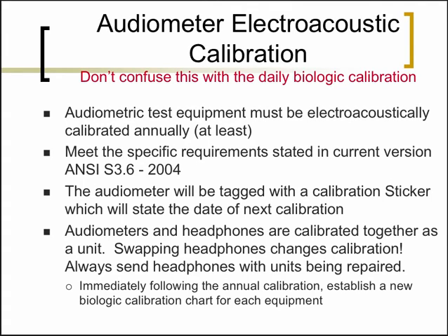So the second type of calibration, the more detailed calibration, is this electroacoustical calibration. This, as I've told earlier, is performed at least annually, and is often required by state and federal regulations to be performed periodically. The intent of this calibration is for the audiological equipment to meet certain standards. And the most recent standard that present-day calibrations need to meet is that of 2004, particularly the standard S3.6 from the American National Standards Institute.